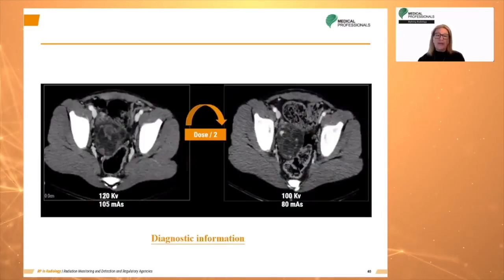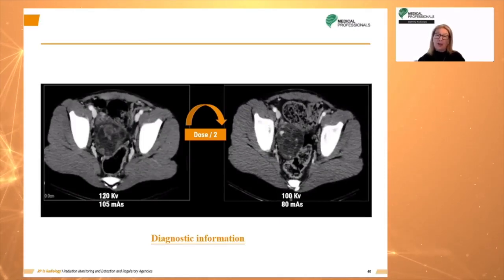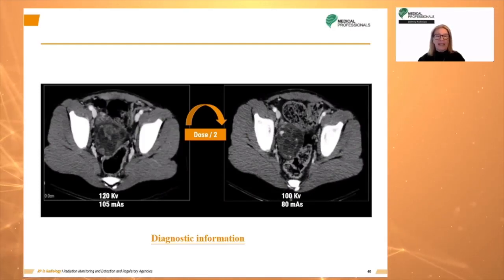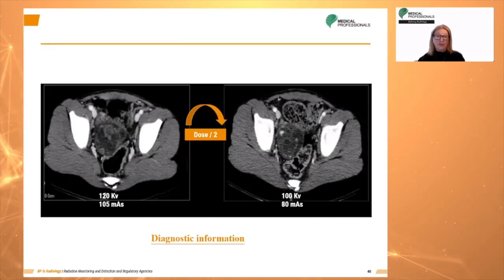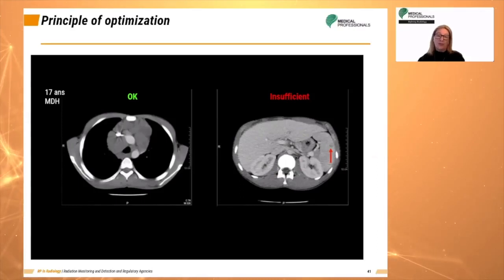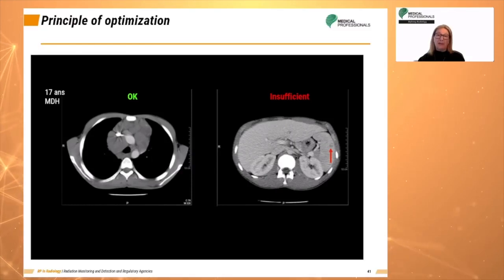Optimization of each acquisition protocol is important to reduce patient dose while keeping good image quality. For example, reducing from 120 kVp and 105 mAs to 100 kVp and 80 mAs still gives a good quality image with a reduction in patient dose. This aligns with the ALARA principle. It is important to note that optimization does not mean underexposure — acquisition constants should not be underestimated to the point of insufficient image quality.